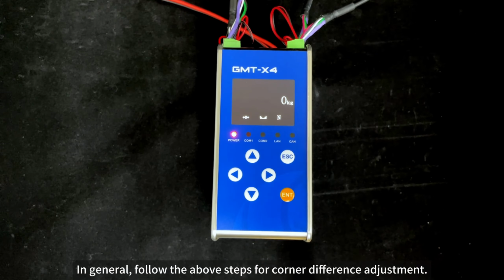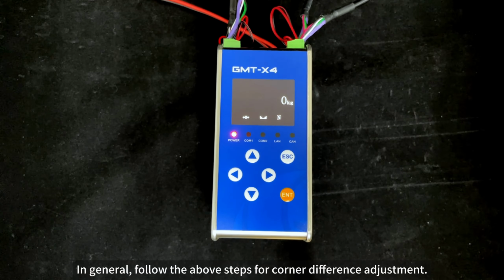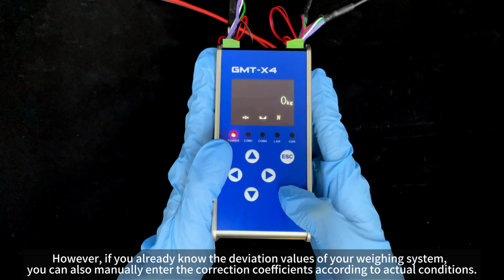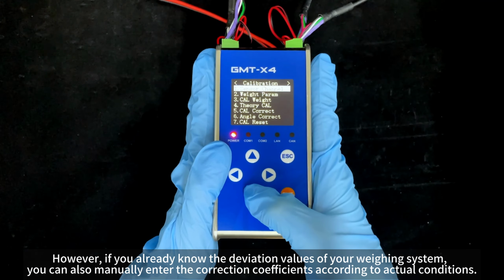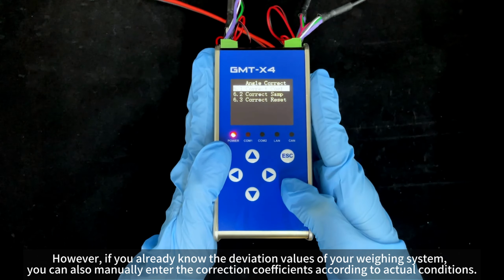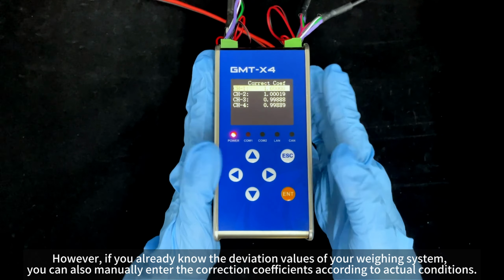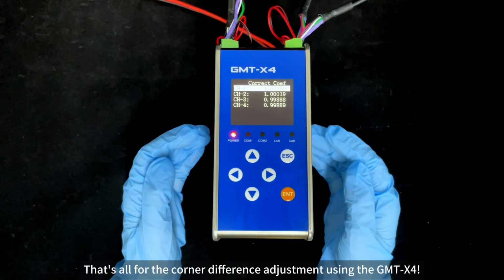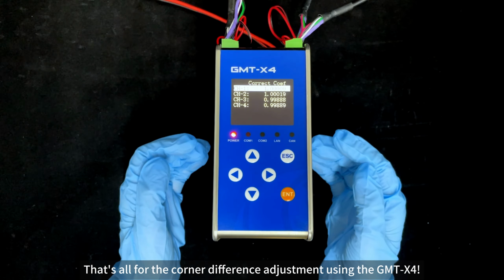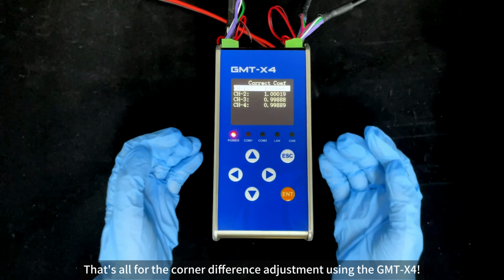In general, follow the above steps for corner difference adjustment. However, if you already know the deviation values of your weighing system, you can also manually enter the correction coefficients according to actual conditions. That's all for the corner difference adjustment using the GMT-X4.